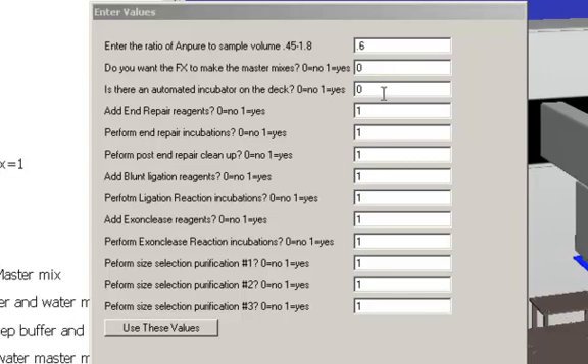The third input is there an automated incubator on the deck. We run with a T-Robot thermocycler integrated on our deck. When we need to incubate something the FX basically puts the lid on the plate, takes the plate to the thermocycler, the thermocycler runs. After it's done running the FX removes the plate from the thermocycler, brings it back on deck. That's fully automated, hands off. I realize probably many people don't have that feature. So I made the option of doing the thermocycler off deck. Basically if you set the automated incubation to a zero, when it gets to the point that it needs to do some incubation, it will pause. It'll pop open a window telling you what parameters, for example, 25C for 15 minutes then cool down to 4 degrees. So basically you have to remove the plate from the deck, put it in a thermocycler, perform that operation. When it's done, put it back on the deck. You simply then hit the OK button and the method continues.